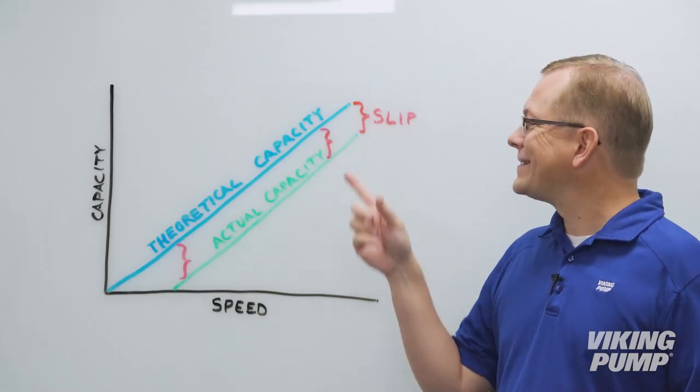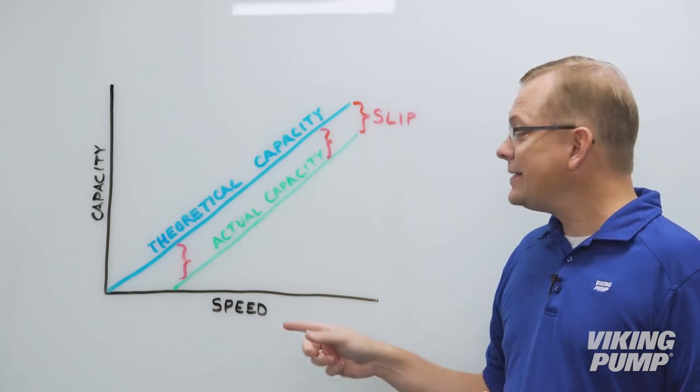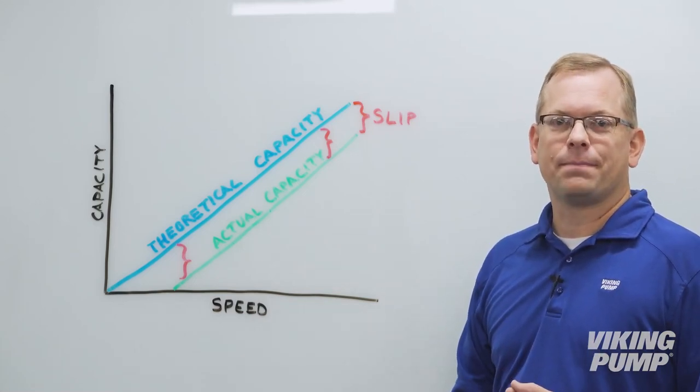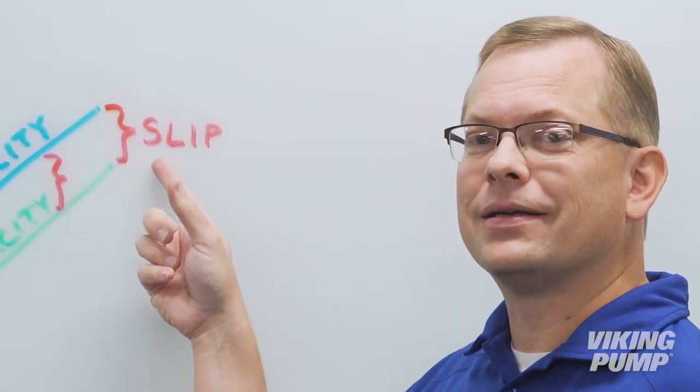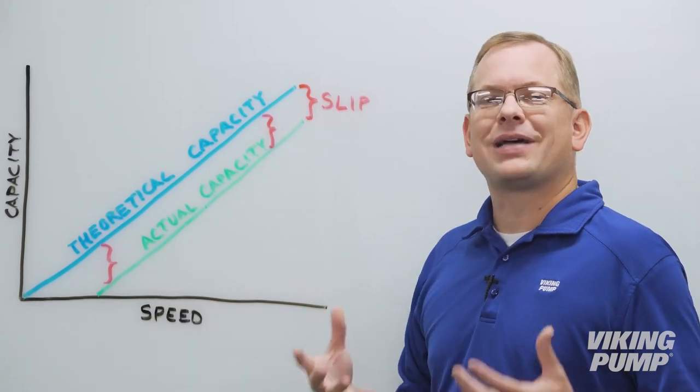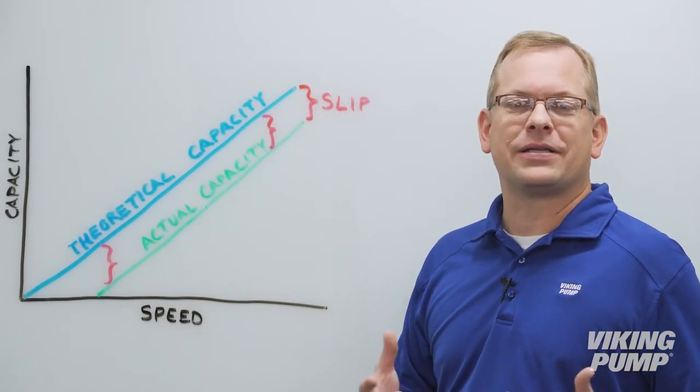It's important to remember that slip is a constant. It's independent of speed, and it stays the same as long as the other variables stay the same. And since slip is constant, it's important to remember that as we move left on the curve and slow the pump speed, it becomes a higher percentage of the overall capacity of the pump.